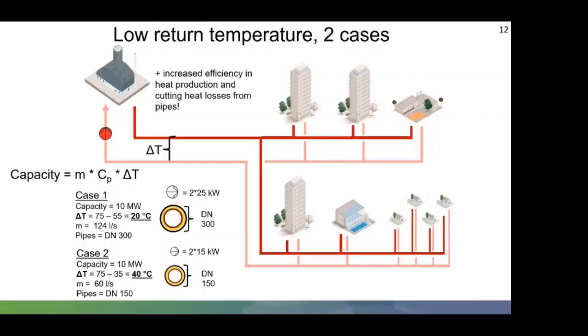So here we are. We have two examples that demonstrate how changes can affect the whole system in a positive way. They both have the same capacity of 10 megawatts. Case one has a primary flow of 75 degrees, return of 55 degrees. This gives a delta T of 20 degrees with a mass flow of 124 litres a second. The pipe size required is DN 300, with pumps of 2 times 25 kilowatts.